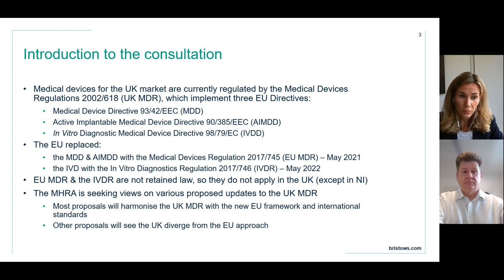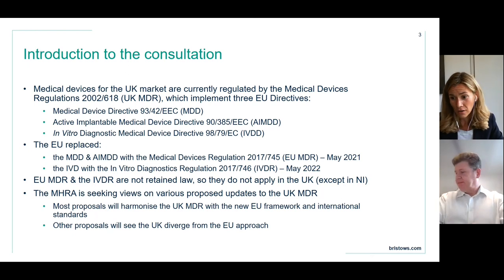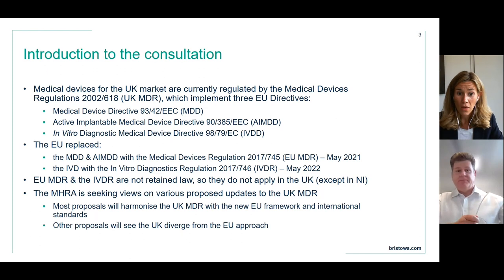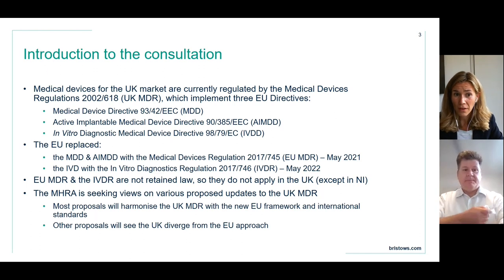The medical devices regulation 2017/745, as I said, applicable ever since May of this year, and the in vitro diagnostics regulation that will start to apply as from May of next year, are not law in the UK. Therefore, the UK MDR applies, and in the region of Northern Ireland, the EU MDR does apply because of the Northern Ireland Protocol.